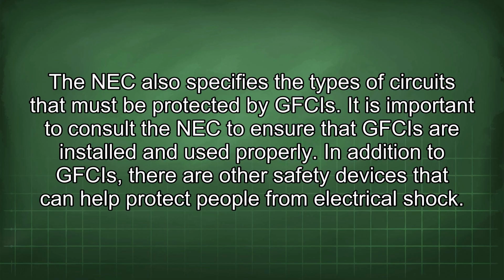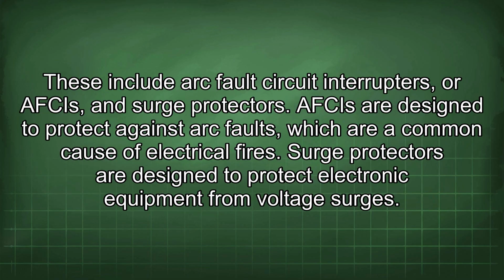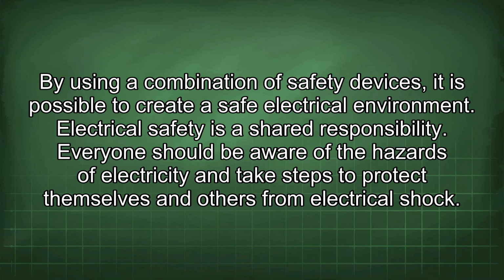In addition to GFCIs, there are other safety devices that can help protect people from electrical shock. These include arc fault circuit interrupters, or AFCIs, and surge protectors. AFCIs are designed to protect against arc faults, which are a common cause of electrical fires. Surge protectors are designed to protect electronic equipment from voltage surges. By using a combination of safety devices, it is possible to create a safe electrical environment.